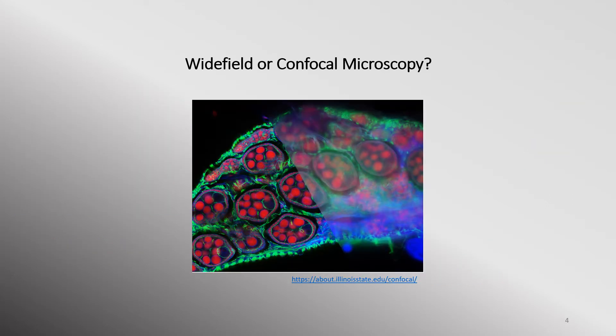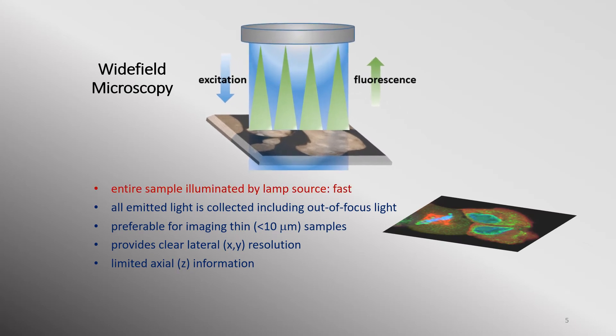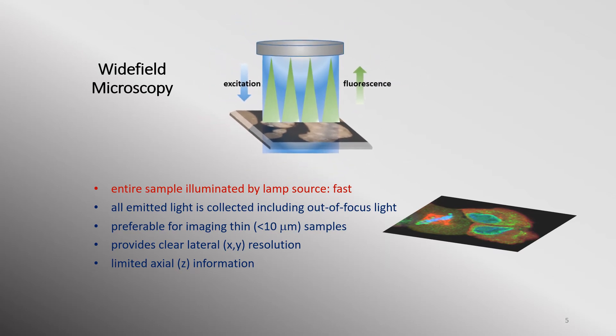In fluorescence microscopy, one of the most common questions scientists face is whether wide-field or confocal microscopy can answer their research problems. Either one could be a better choice — it all depends on sample, application, the required data, as well as data quality. In a wide-field microscope, the entire focal volume is illuminated, but this creates blur from areas out of focus above and below the image plane. When samples are thin and flat, wide-field microscopes are preferred as they provide good resolution in the XY plane. An example would be a single layer of cultured cells or a very thin tissue sample.